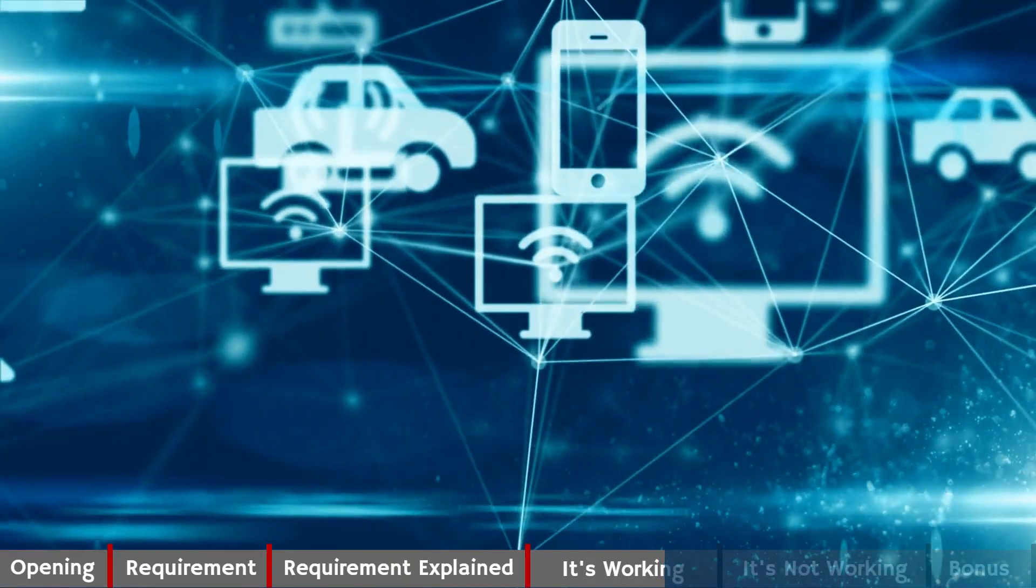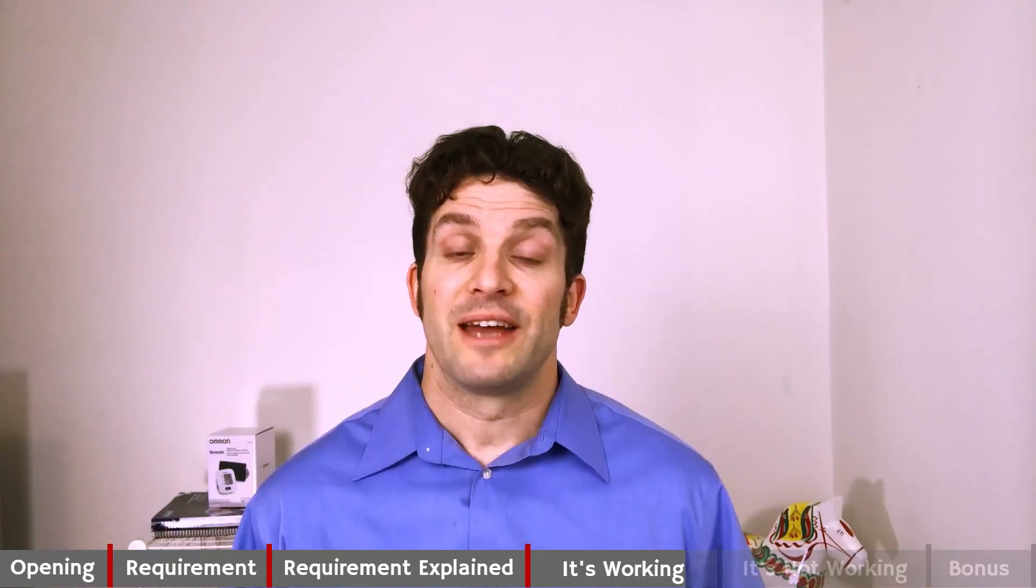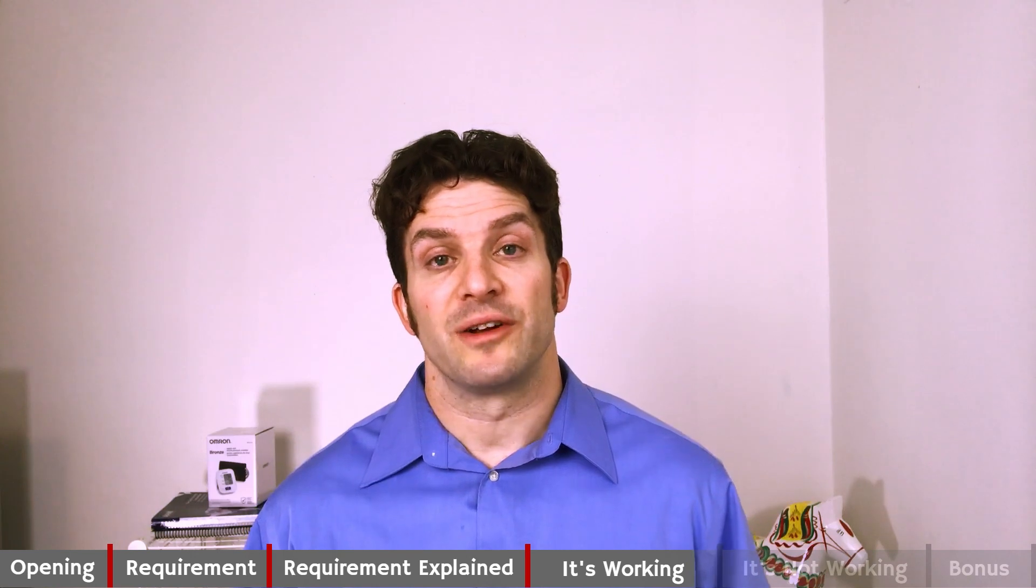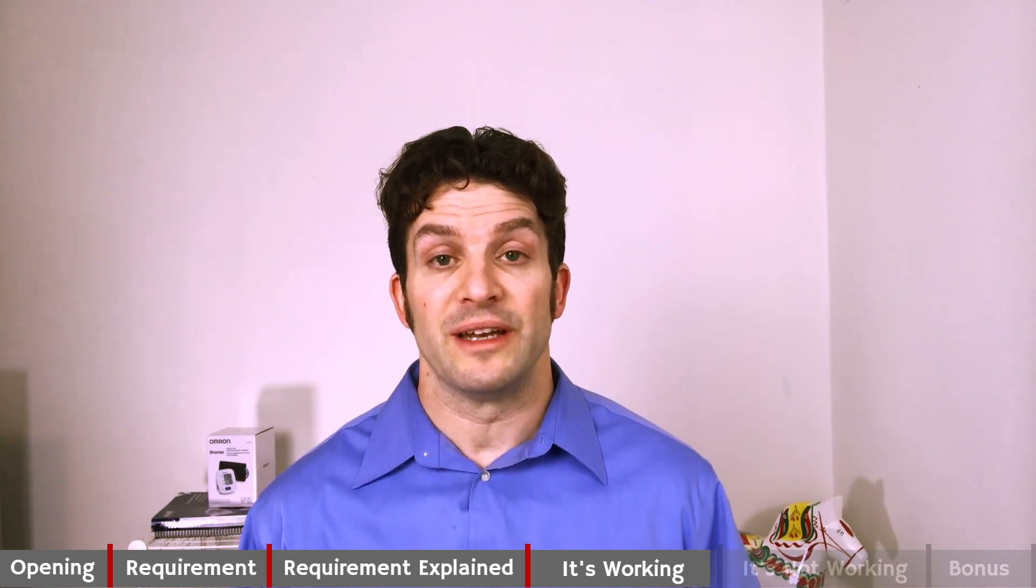If my device communicates with other devices, I'm testing that communication during the validation. And finally, all defects found during the validation are documented, reviewed, risk determined, and they are addressed before my product launch.